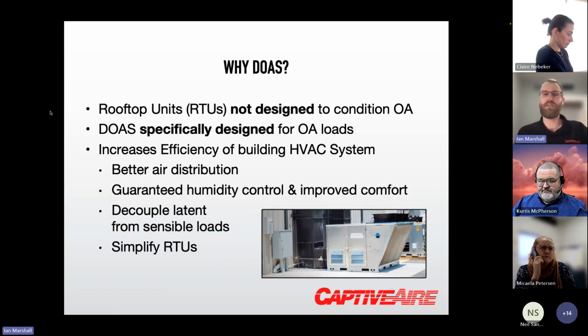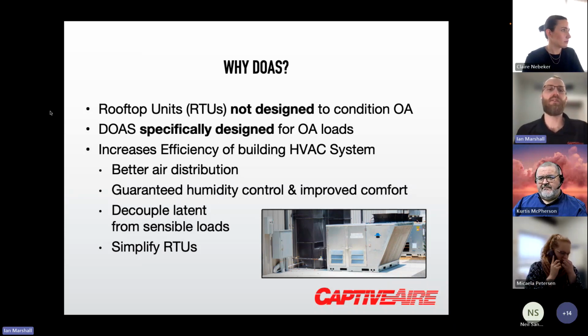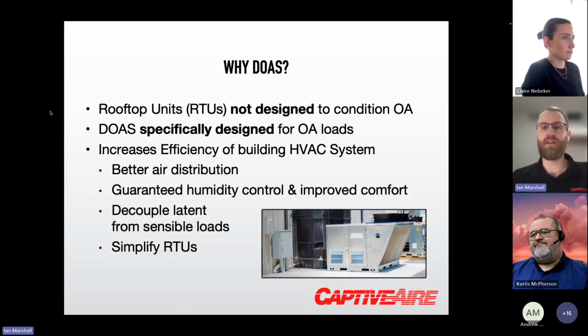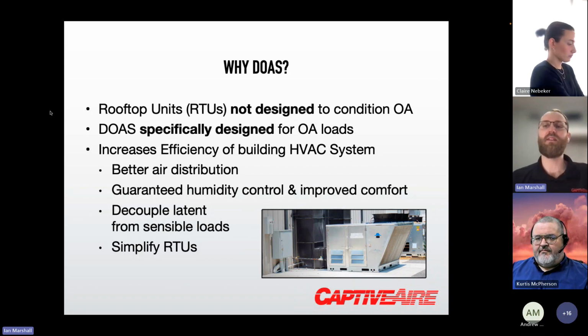So why is DOAS used, or what really is DOAS compared to what someone might define as a traditional RTU or rooftop unit? Generally, rooftop units or RTUs are less geared towards conditioning outdoor air, where DOAS, or this unit in particular, is catered towards handling higher volumes of outside air, up to 100% outside air. With the way that designs have been going, we see a lot of what they call decoupling the sensible and latent loads, or just decoupling the outdoor air ventilation loads from the internal space loads.